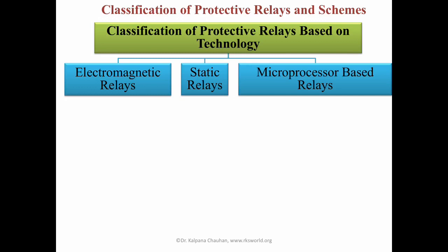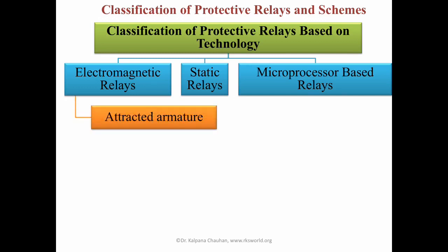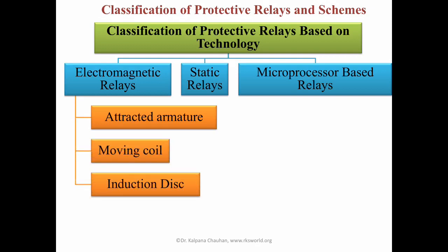Microprocessor based protective relays are the latest development in this area with the development in VLSI technology. Their applications to the problems of protective relaying schemes are of current interest to power engineers. The inherent advantages of microprocessor based relays over static relays with a very limited range of applications are attractive flexibility due to their programmable approach. The electromagnetic relays again can be classified as attracted armature type, moving coil type, induction disc type and induction cup type relay.